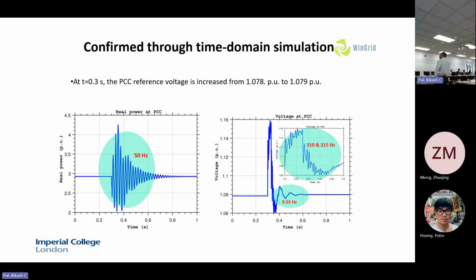This is definitely not harmonics. The 310 can never be harmonics, it has to be either 300 or 200. So that's the resonance, and these are the medium frequencies being excited.